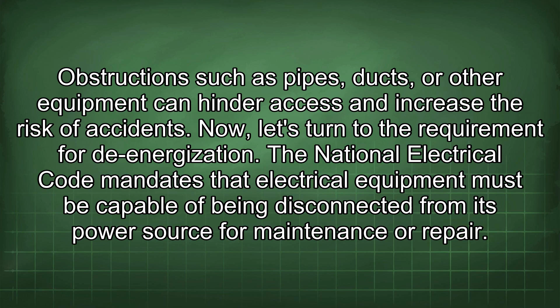Now let's turn to the requirement for de-energization. The National Electrical Code mandates that electrical equipment must be capable of being disconnected from its power source for maintenance or repair. This is typically achieved through a disconnect switch or circuit breaker located within sight of the equipment. The disconnect switch or circuit breaker must be readily accessible and clearly labeled to indicate its purpose.